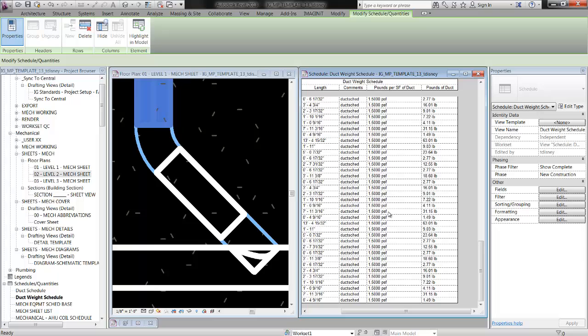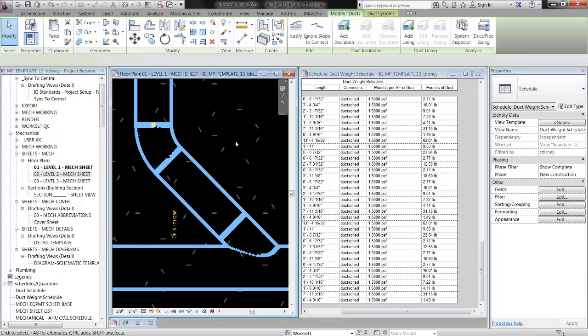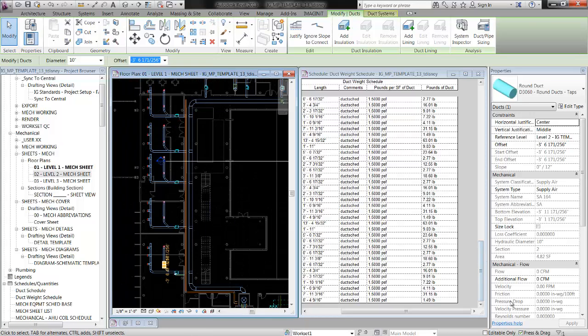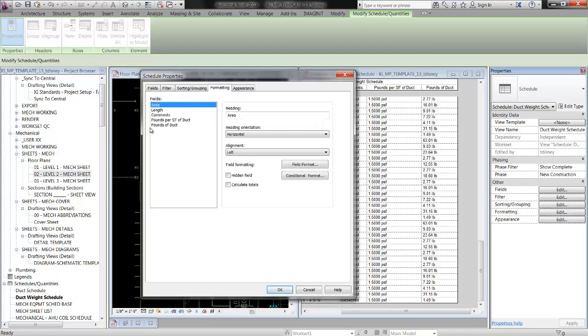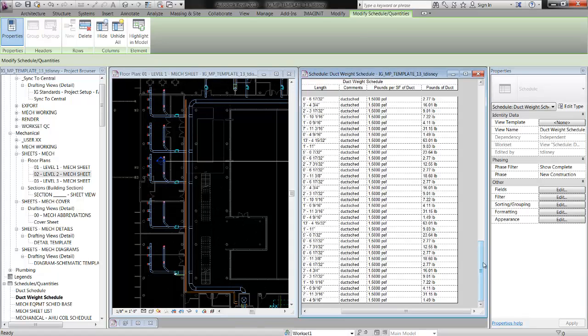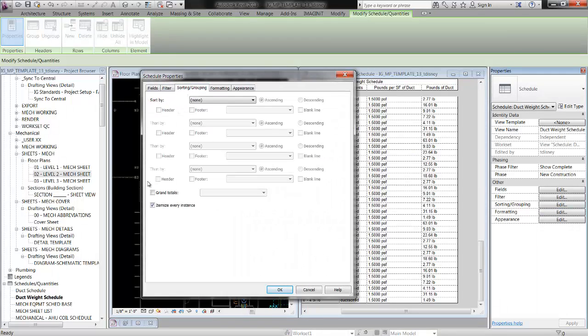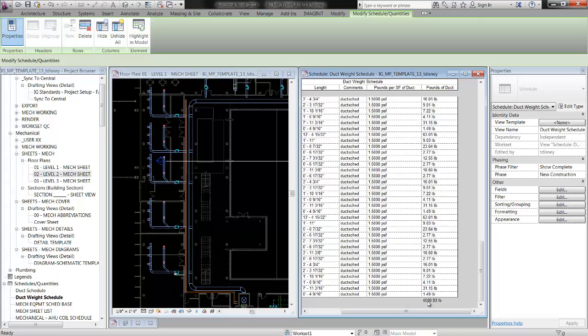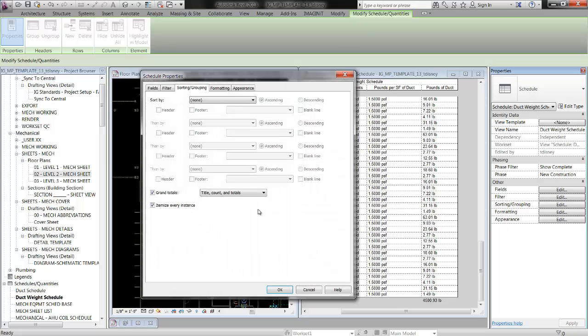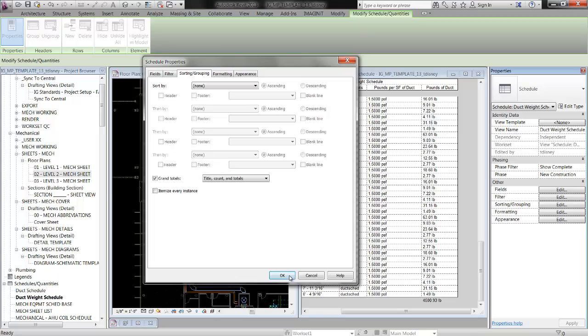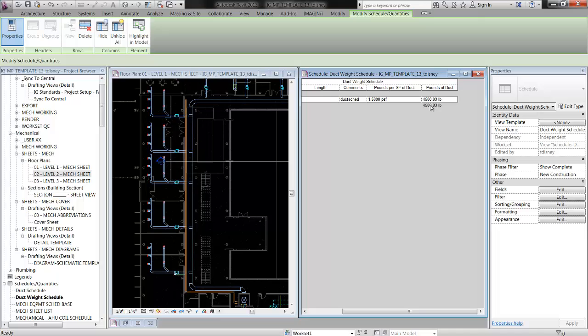I don't really care what each individual duct weight is — I'm just trying to get the weight for all of the duct on this floor. So I'm going to go back into my schedule, go to formatting, and over 'pounds of ducts' I'm going to click calculate totals. There's one more thing in sorting/grouping — I have to hit grand totals. At the bottom of my schedule you can see that all the duct work on the first floor is 4,500.93 pounds. I can also go back into schedule properties, sorting/grouping tab, and uncheck 'itemize every instance,' which collapses them all into one row — a lot nicer.